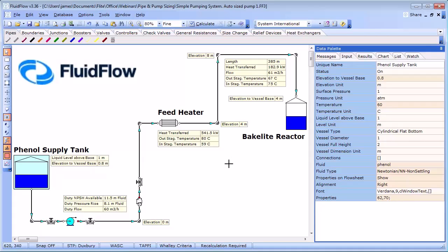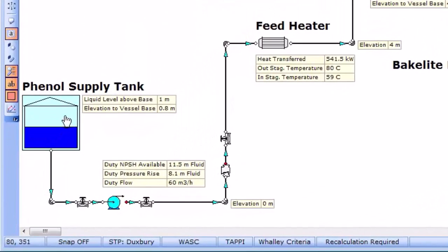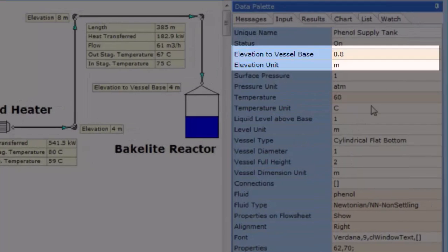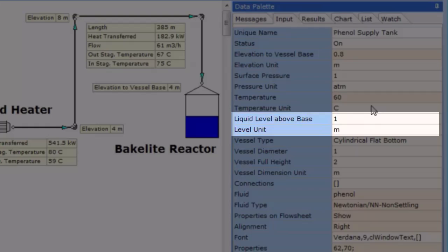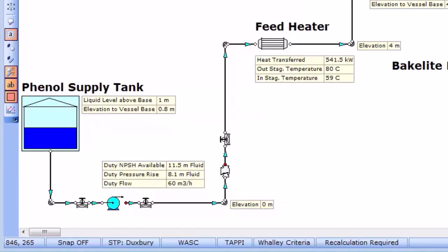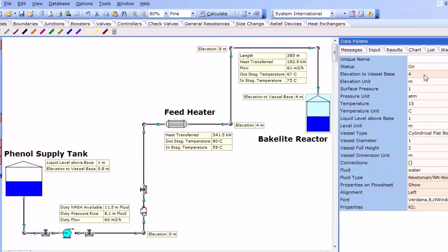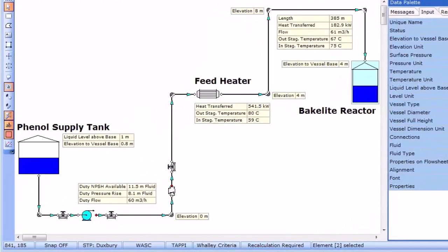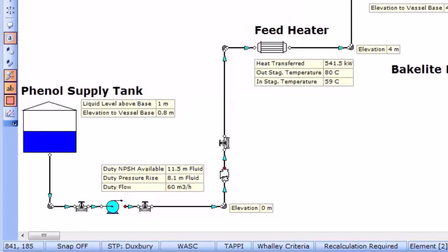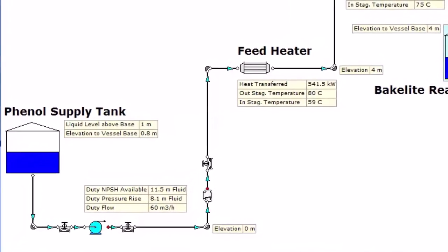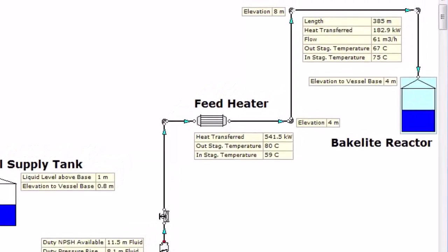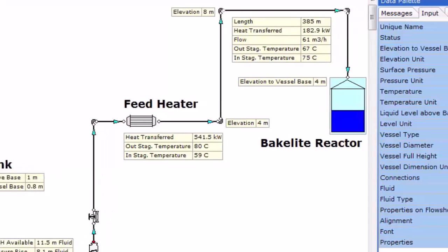Let's now use this design case to examine the steps involved in the process design of a liquid transfer system. Fluid in this case is phenol which is pumped from a storage tank to a reaction vessel. The storage tank contains phenol at 60 degrees C and has an elevation of 0.8 meters with a liquid level of 1 meter. The pump has an elevation of 0 meters and the reaction vessel is positioned at an elevation of 4 meters. The connected pipework has a total length of over 385 meters and includes a feed heater, a series of bends, a check valve and a number of diaphragm isolation valves. The feed heater in the line increases the temperature of the phenol from 60 to 80 degrees C prior to transfer to the reactor.